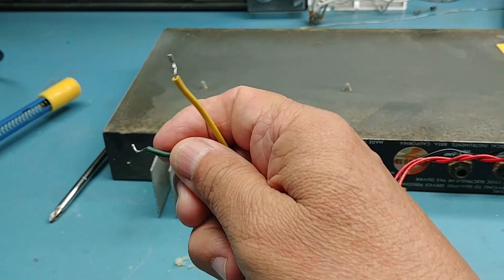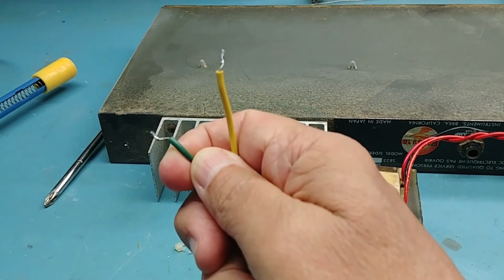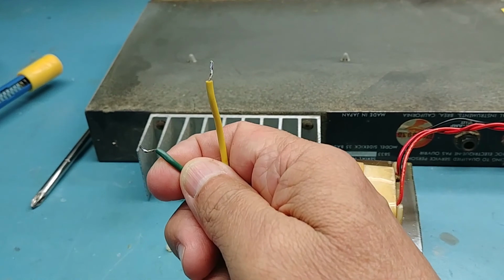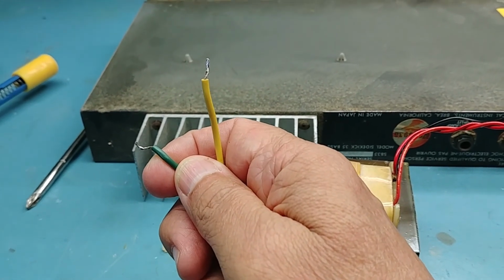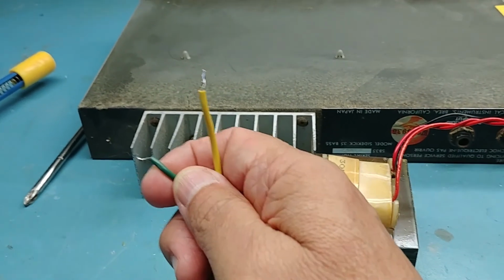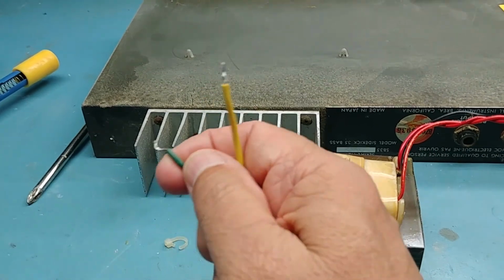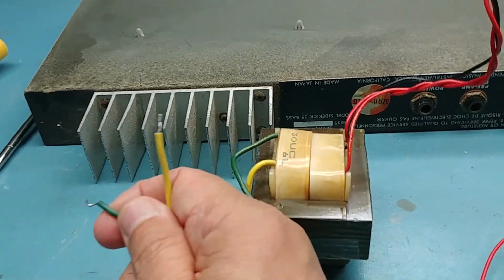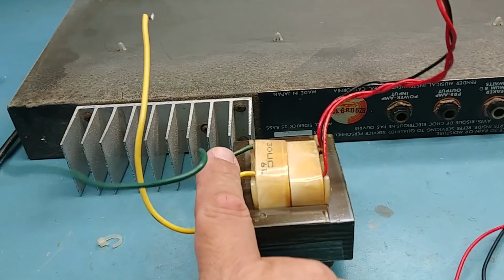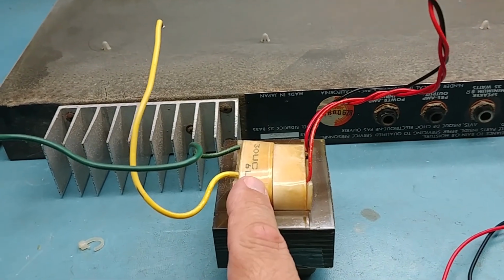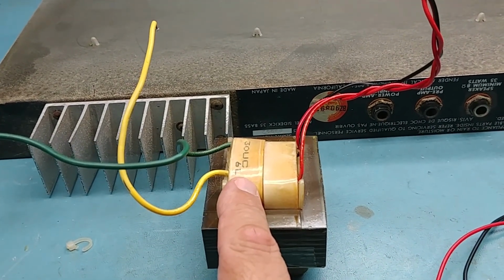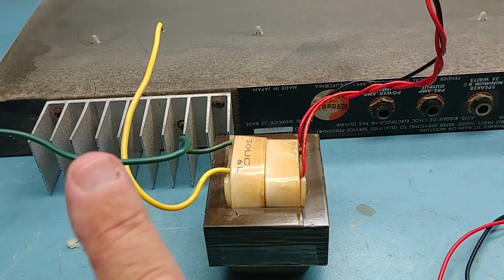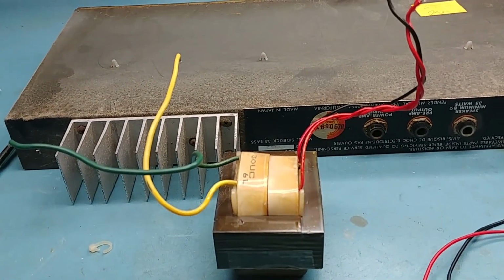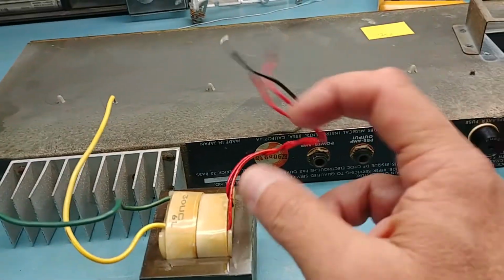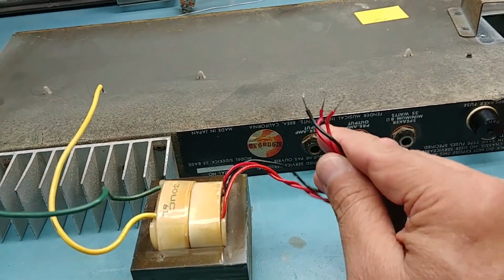So when I tested this, these two primary wires, which, like I mentioned, were one coil, should measure a very low resistance and show that they're connected. When I measured them, it measured as an open circuit. There was infinite resistance between these two wires, which tells me that this primary winding has failed in some way. It's either opened up on its own because of a physical problem or some kind of poor workmanship, or it has been burned up. Checked the secondary side; it was fine.